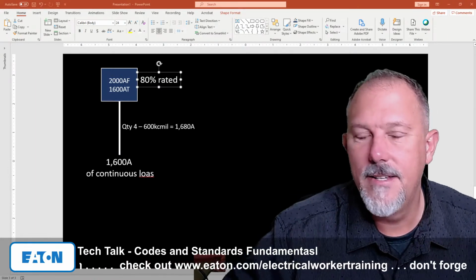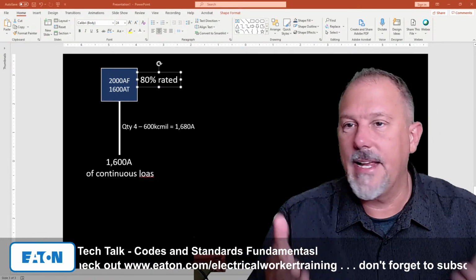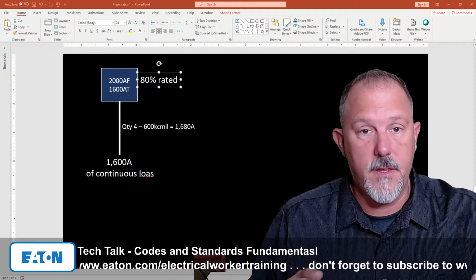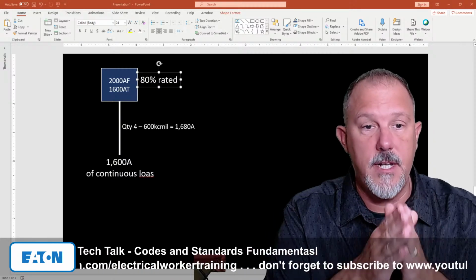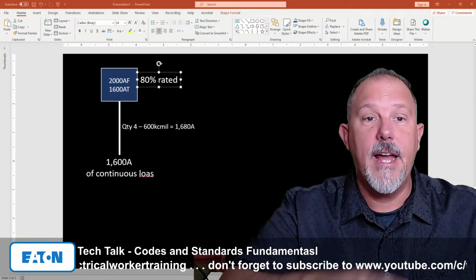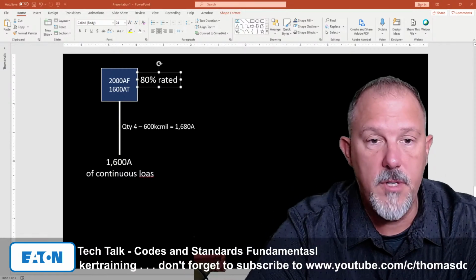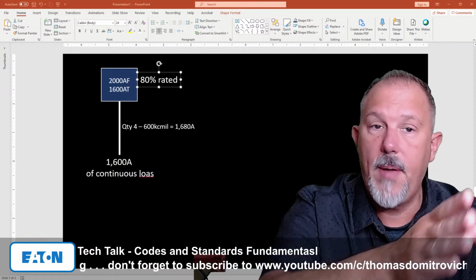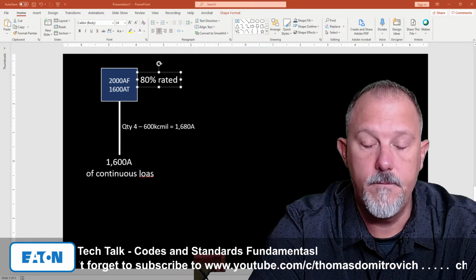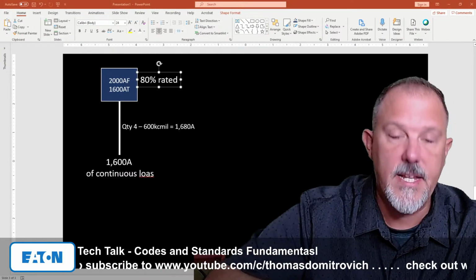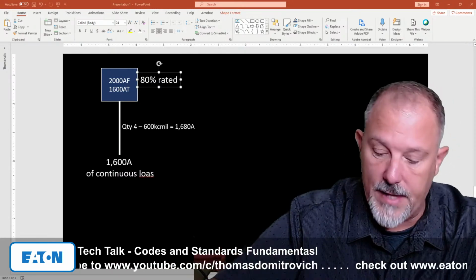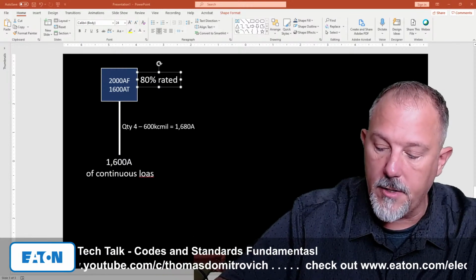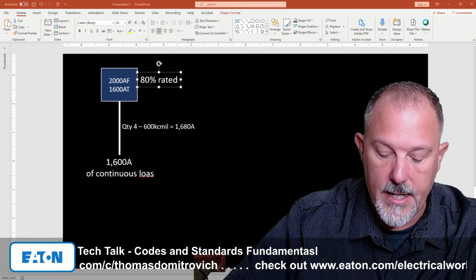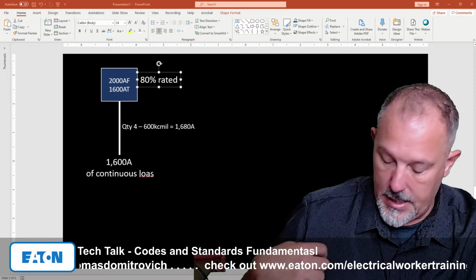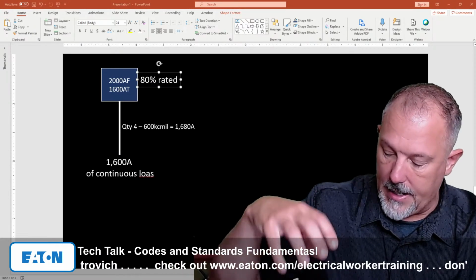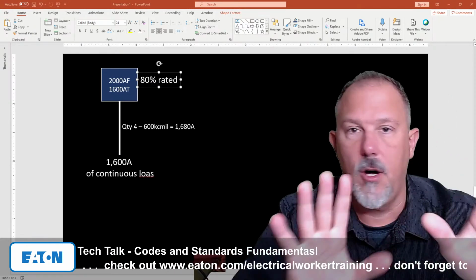Nick Tesla, do you think this is fine? I can't remember who asked this question. Do you think that this is perfectly fine? I have 1600 amps worth of continuous load. I have 4 600 kcmil conductors. Total ampacity of that, if I'm following table 310.16, the conditions of use would be not more than 3 current carrying conductors in a raceway, cable, or earth, directly buried, and I'm within the 30 degrees C, all that good stuff.